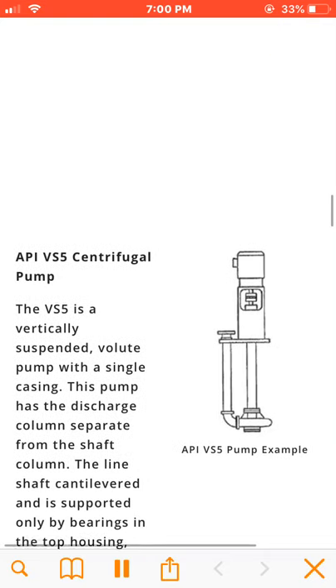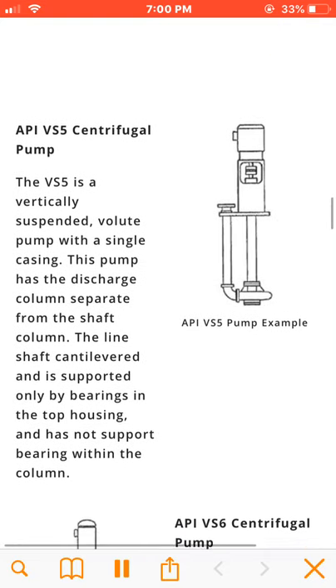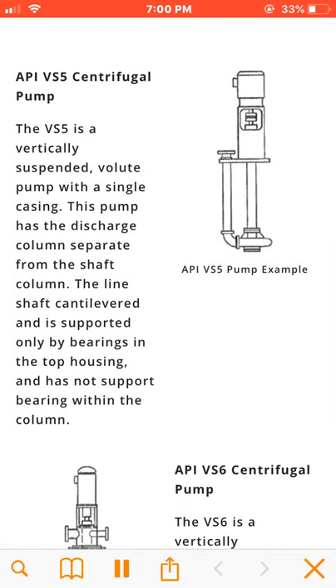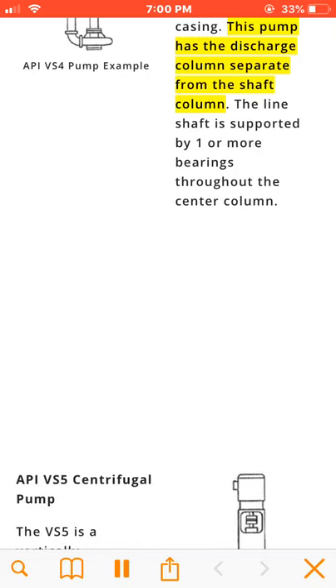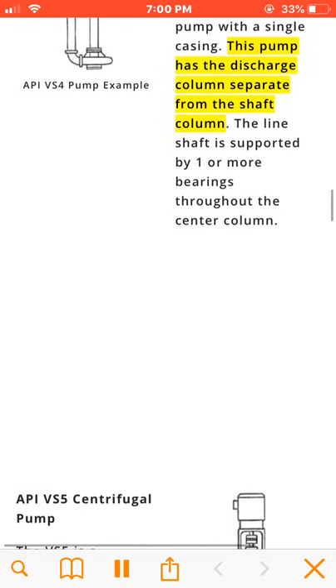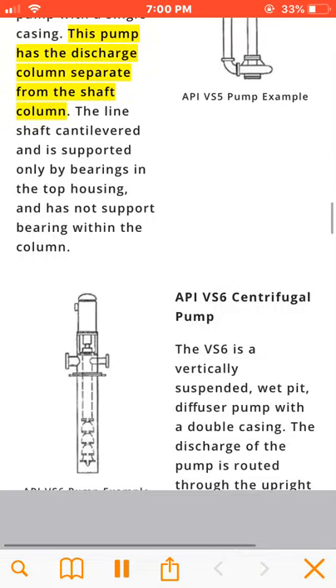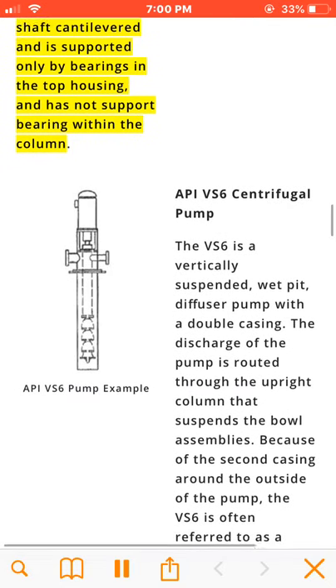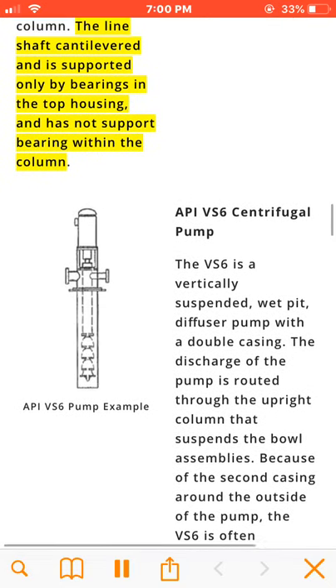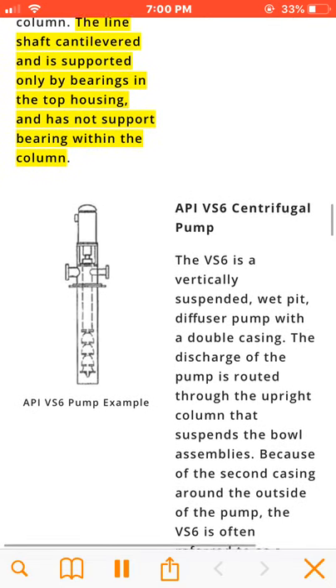The VS5 is a vertically suspended volute pump with a single casing. This pump has the discharge column separate from the shaft column. The line shaft is cantilevered and is supported only by bearings in the top housing, with no support bearing within the column.